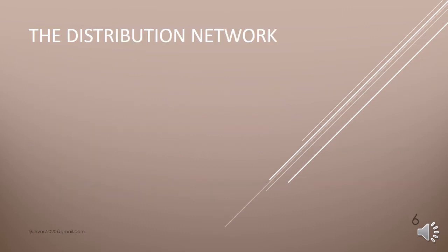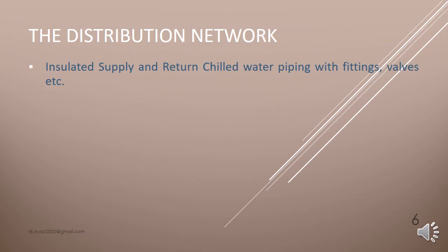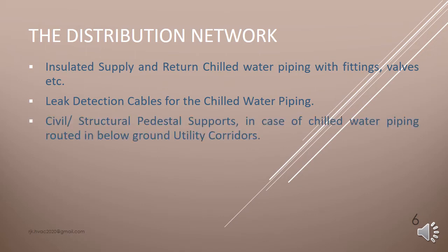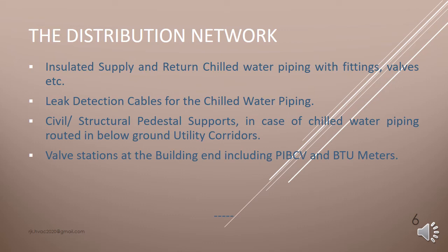The distribution network. It comprises of insulated supply and return chill water piping with fittings, valves, etc., leak detection cables for the chill water piping, civil or structural pedestal supports in case of chill water piping routed in below ground utility corridors, valve stations at the building end including PICV and BTU meters.